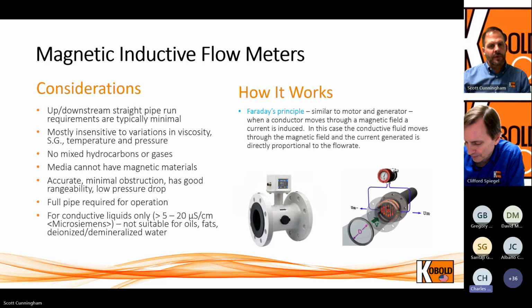Back to the magnetic inductive meter considerations: it's really not suitable for hydrocarbons or gases, and the media cannot have magnetic materials in the flow. It does have really good rangeability, low pressure drop, and minimal obstruction. And again, like all of our flow meters, it requires a full pipe for operation.